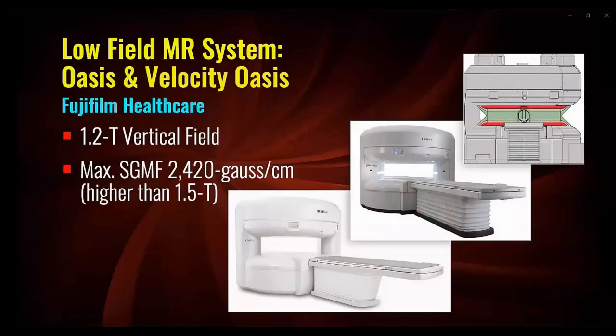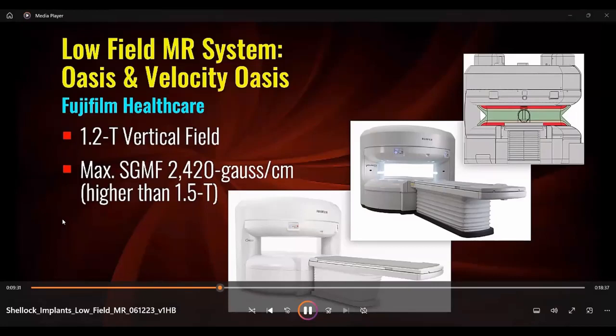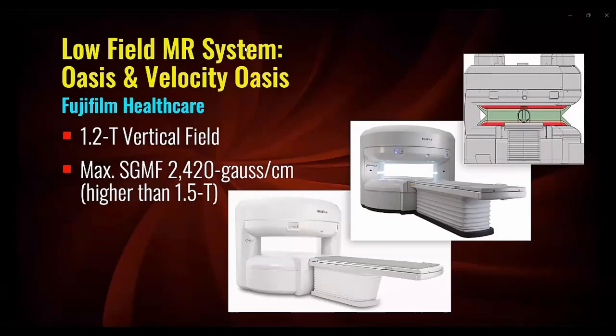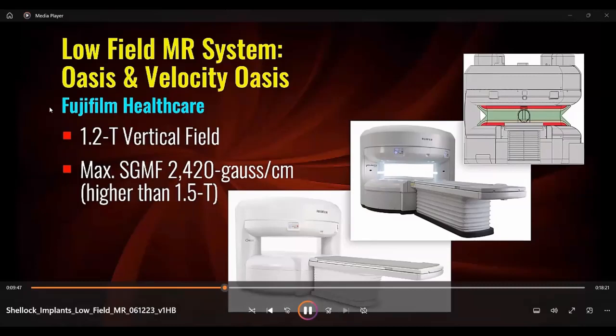Finally, there are MR systems that operate just under 1.5 Tesla, namely the OASIS and the OASIS Velocity vertical field 1.2 Tesla scanners from Fujifilm Healthcare. These systems have a maximum spatial gradient magnetic field of 2,420 Gauss per centimeter, which is higher than the maximum spatial gradient magnetic field values that are associated with 1.5 Tesla horizontal field scanners.